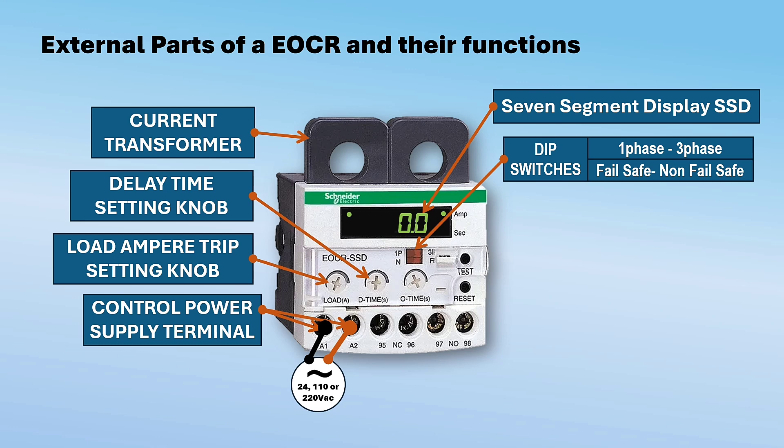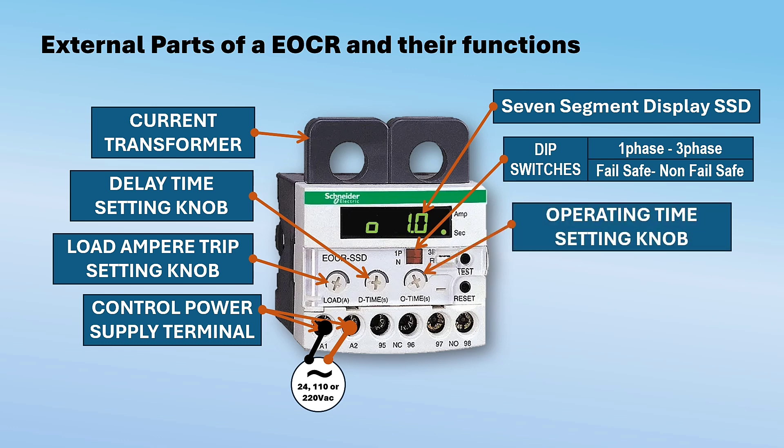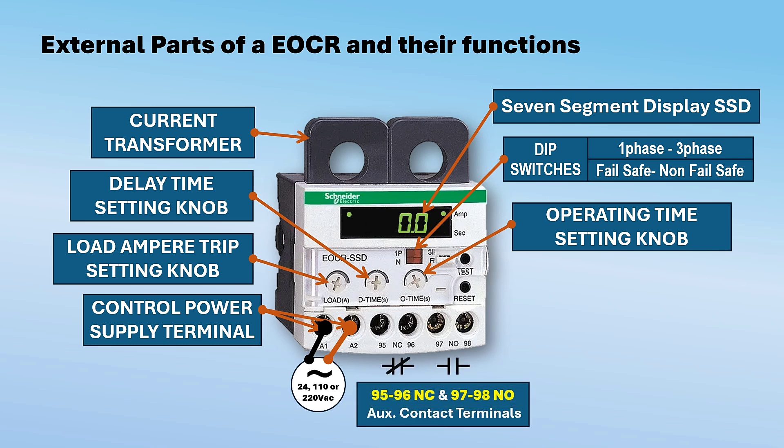O-time or operating time knob — it sets the time in seconds during which the current should be over the ampere setting continuously for the entire operating time period before the EOCR trips. Auxiliary contacts — terminals 95 to 96 are normally closed and 97 to 98 are normally open. These contact statuses change when the EOCR trips.